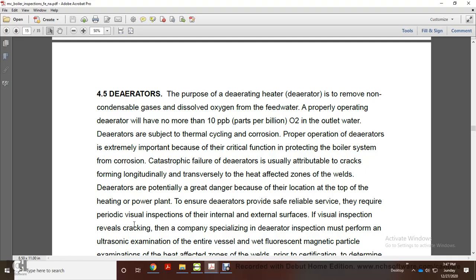Alright, 4. De-aerators. The purpose of the de-aerating heater, or de-aerator, is to remove non-condensable gas and dissolved oxygen from the feed water. A properly operating de-aerator will leave no more than 10 parts per billion oxygen in the water. De-aerators are subject to thermal cycling corrosion. Proper operation is extremely important because of the critical function of protecting the boiler system from corrosion. Catastrophic failures of de-aerators are usually attributable to cracks in the longitudinal and transverse weld heat affected zones. A de-aerator's location on top of the heating power plant makes it a potentially greater danger.